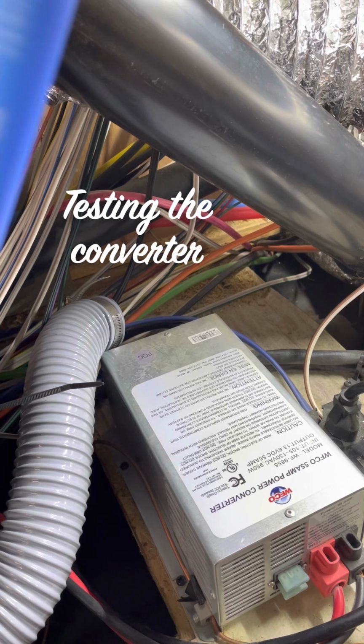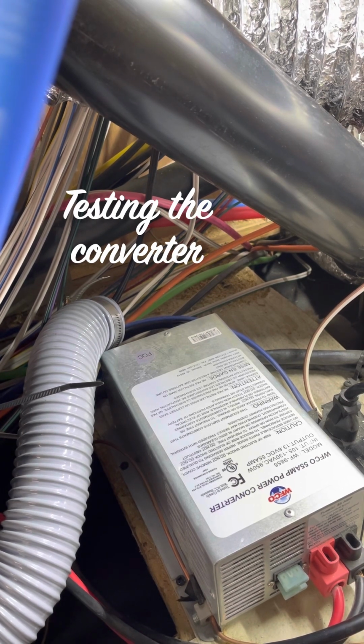To check that, carefully disconnect the ground wire, which is the black one, from the output of the converter. Then you can check the voltage. If there is none, the converter is bad and it's time for a new converter. If there is, you have a wiring problem. It's rare, but you could have two wires that have rubbed together and are drawing enough current to drop battery voltage, or you could have a wire somewhere that is too small and is overheated and adding extra resistance.